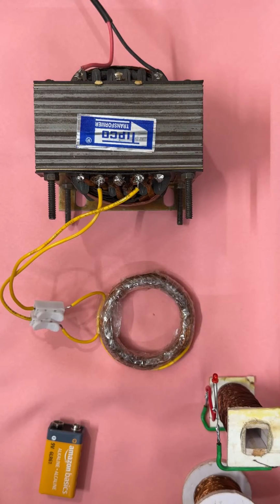This 11 kV line or 33 kV line which runs in your cities for point to point power comes from your nearby grid, and your grid has got gigantic transformers with input as high as 132 kV. That means 132,000 input volts to those transformers, and output is 33 kilovolt or 11 kilovolt as required. So from your grid, which is at a distance from your cities, you gather a 33 kilovolt line running over to your cities, and from the 33 or 11 kV nearby transformers, we get 220 or 440 volt supplied to your domestic power supply.